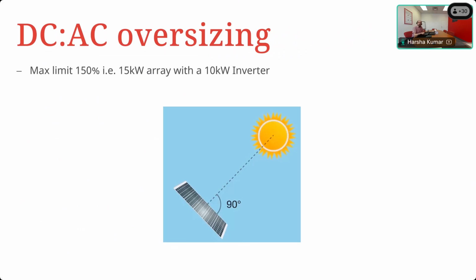Were there any questions? A couple more. Will we need a separate switch to activate the rapid shutdown? Are the Quattros and Duos being phased out? We're not phasing them out, but you will need a separate switch. We are actually coming up with a Duo and a Quattro with higher current capacity, because the current Duos and Quattros have their channel capacity limited to 25 amperes, which typically comes down to a short circuit current of just over 10 amperes. So if you've got higher power panels you intend to use, you'd be limited to one string per channel, which is why we're coming up with a newer version.